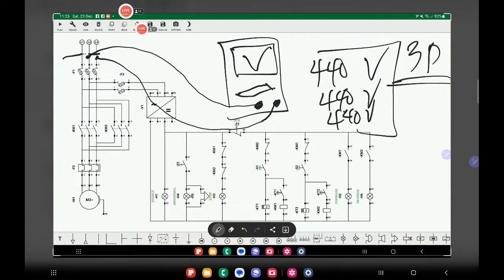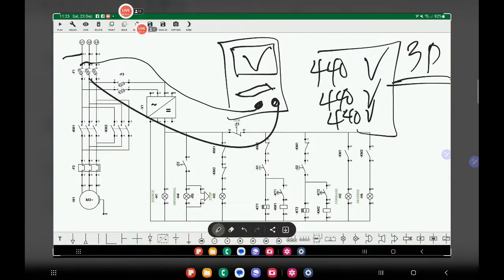Now, I need to check if I am having single phasing on the F1. The best way is to leave one of the probes on number 1 and put the second probe on number 4 on line 2. You should be measuring 440 volts on your multimeter, because if F1 is closed, assuming it is activated, you'll have continuity on the whole line. So it's just like measuring line-to-line voltage.